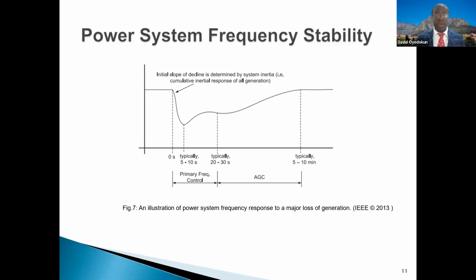If we don't have that reserve capacity to meet the 900 megawatt deficit, the network will go through a load shedding or load reduction process, dropping some load to ensure the balance between generation and load is kept at all times. The next phases speak to various elements of frequency control, from primary to secondary to tertiary across various time windows, to ensure that balance between generation and load is met.